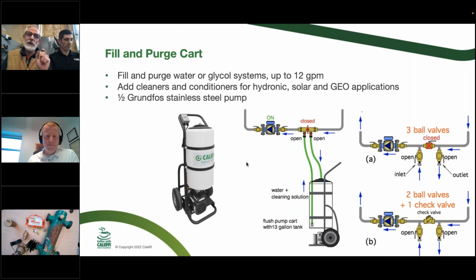Now, if you had a system that you could break down to one zone at a time, okay, I'll do one zone and the next zone and the next zone, which could take you all day, you might get away with just the pump or with just the fill valve. But when you start talking 1.25" piping and stuff like that, you're going to need a little bit more horsepower. For sure. We can help you.